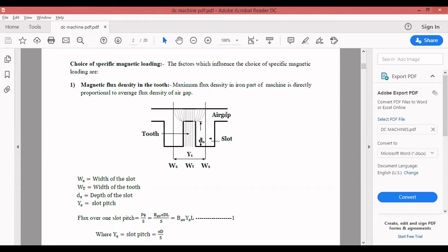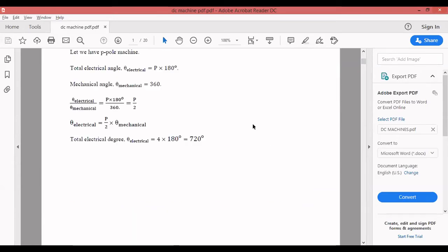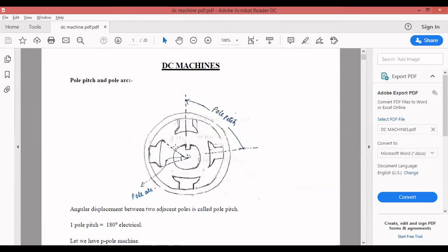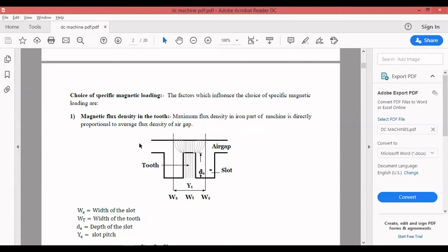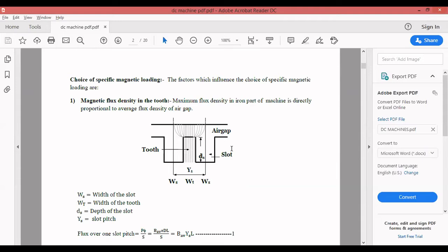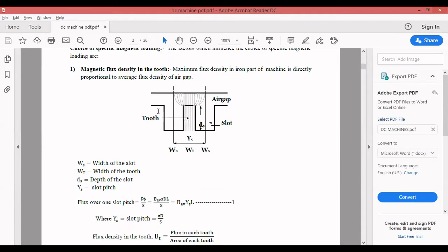The average flux density in the air gap is given by the formula B_av = p * phi divided by (pi * D * L). The average flux density in the air gap depends mainly on the flux produced by the field. So what are the factors that influence specific magnetic loading? The first one is magnetic flux density in the teeth. The maximum flux density in the iron part of the machine is directly proportional to the average flux density in the air gap.